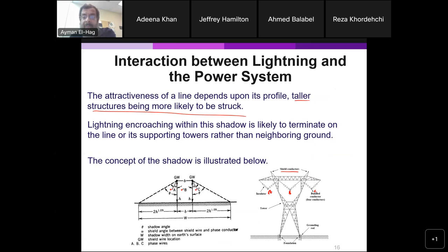However, now we have something called the shadow. What is the shadow here? This, W, is your shadow. This whole thing is your shadow. If the lightning hits in this area, it will most likely terminate on the line or the supporting tower. So if a lightning strike hits within this vicinity, most likely it will be hitting the structure or the tower. If it is outside this, most likely it will not hit the tower, but it will hit the ground or anything around the tower. The shield here is there to protect the overhead lines from the surge that can come and hit your overhead line.